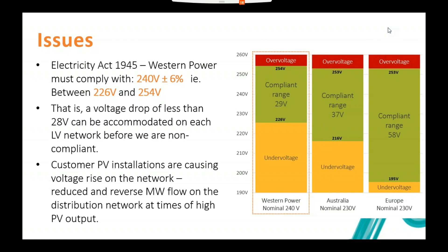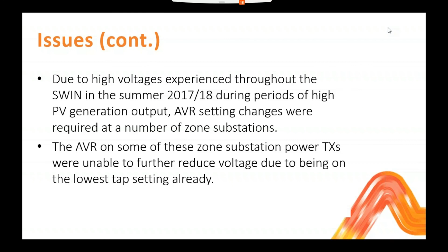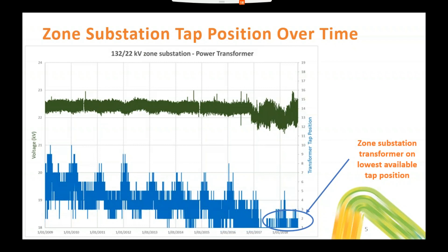We started to see some real problems in 2017 and '18, where we had changed the settings of our zone substation AVRs and tried to reduce the voltage that way. Here's a capture of one of our substations - the top line shows the voltage control, the bottom blue is the tap position on those zone substation transformers. You can see over time they've tended to come down from the higher transformer tap positions, and by '17, '18 we hit the bottom tap and struggled to achieve voltage control, as they can't go any further down from the transmission supply side.